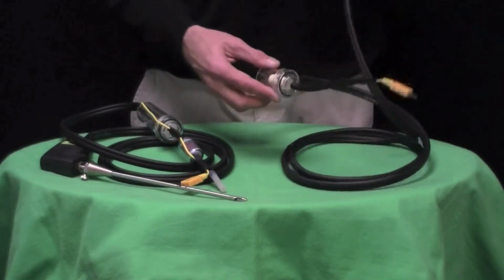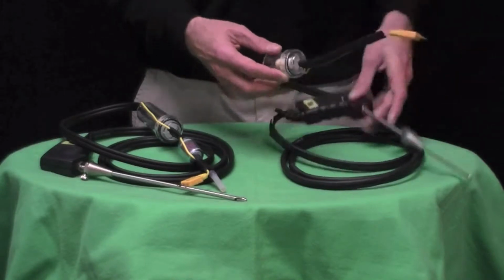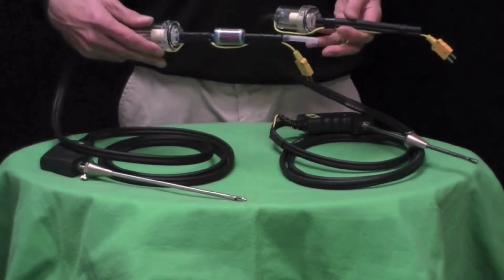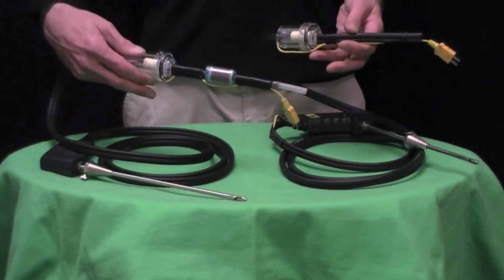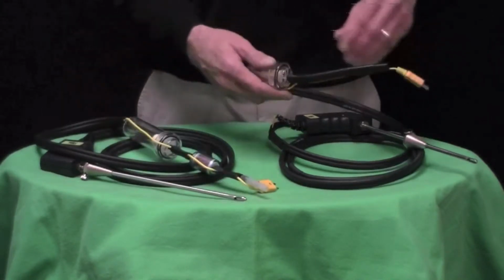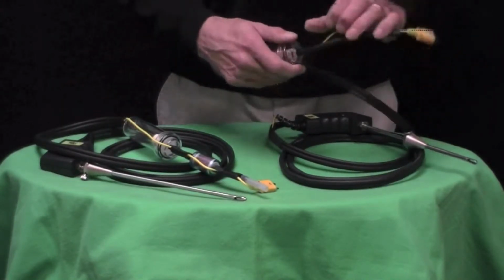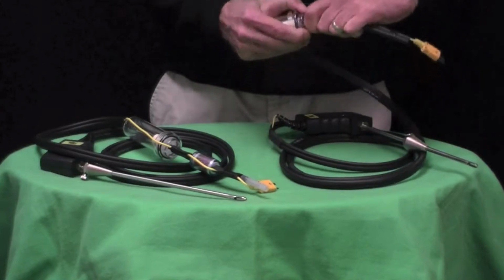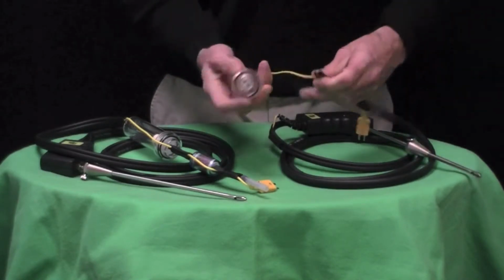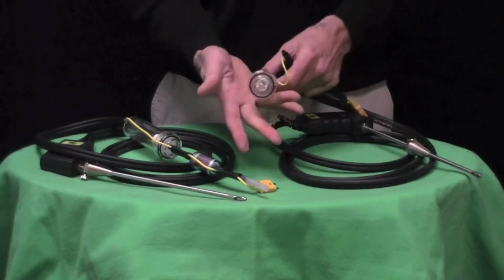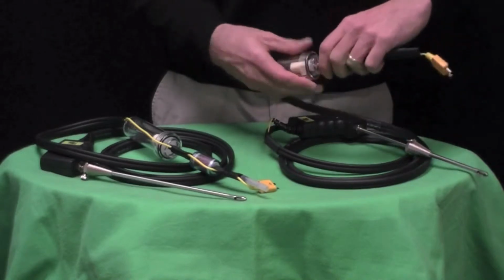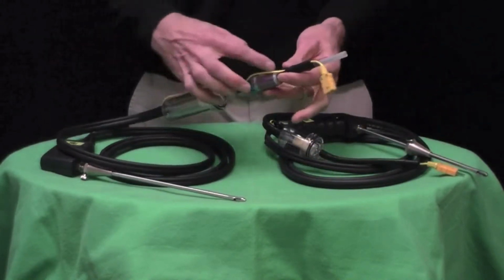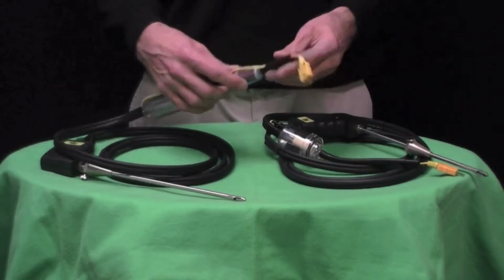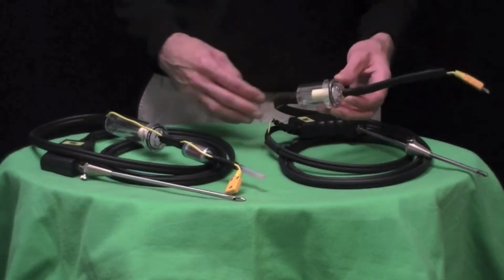This is the standard flue probe, and this is the flue probe with the A773 sulfur filter. All that needs to be done is to take out the water trap by pulling apart the hose from the water trap itself, then replacing it with the A773 sulfur filter. It's bidirectional, so either way you put it in is fine.